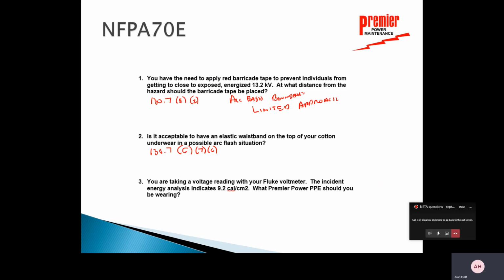Number 3, you're taking a voltage reading with your Fluke voltmeter. The incident energy analysis indicates 9.2 calories per square centimeter. So this is a question that's aimed toward the NETA test, but also toward our own standard procedures. If you look at this, it says 9.2, and we've been working for the last couple of years to get away from the old categories, because labels are going to be changing. It's not going to be categories 1, 2, 3, 4, but it's going to give us the incident energy level of the clothing requirement. This one says it's 9.2 calories.